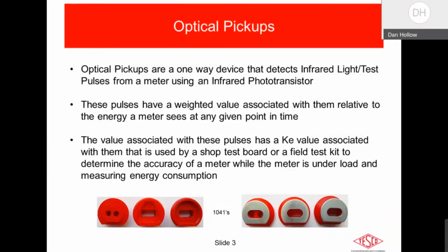So as the meter outputs a pulse, each one of these pulses has a weighted value associated with it relative to the energy that the meter is seeing at any point in time. And that value of the pulse has a K sub E value associated with it that is used by a shop test board or a field test kit to determine the accuracy of the meter. So these pulses get counted.